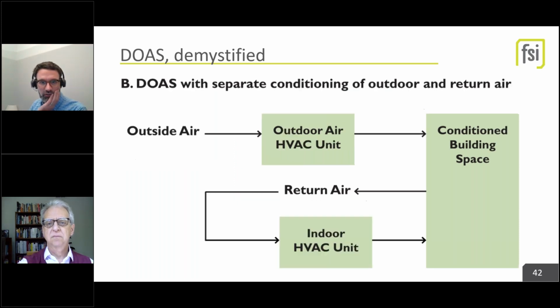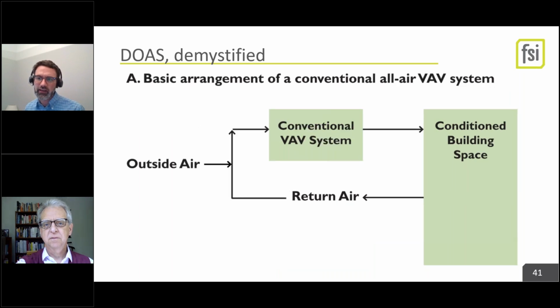Let's hit the next slide. So the only difference between what we used to do and what we do now is that we introduce outside air through a separate unit separately into the conditioned space. And that's important to know. I still see some people, when we do a code review, trying to plug outside air into the back of a fan coil, and that's no longer allowed. You need to put it directly into the space. But that's it. That's the difference. Instead of mixing the return and the outside together, we deliver it separately through a separate unit so we can do the conditioning. And importantly, go to the next slide.